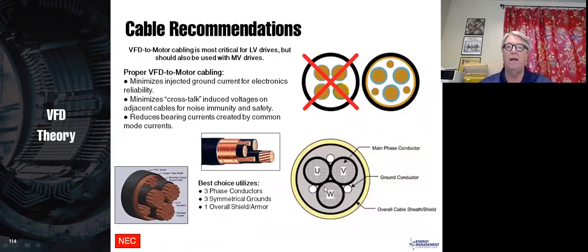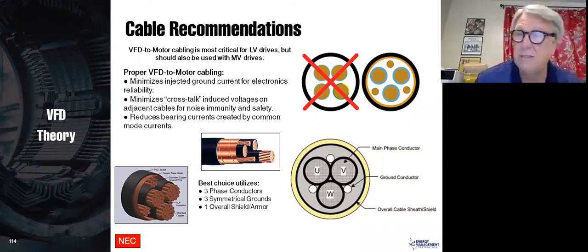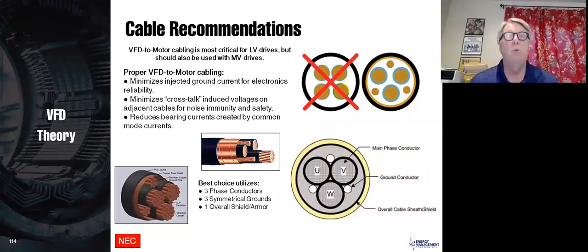If you have a good cable like this, the three phases are symmetrical in a triangle shape. Instead of having one ground, you actually have three grounds. Some VFD cables only have one ground, but the best is to have three grounds. And then you have an overall cable sheath. So this keeps the voltages balanced. It will help you with your bearings. It will keep the motor windings balanced inside, and it will help prevent radiation of that PWM noise going airborne through the cable. So most people installing drives do not use this, but I do recommend it, and of course ESA recommends it, so there's kind of an official recommendation.